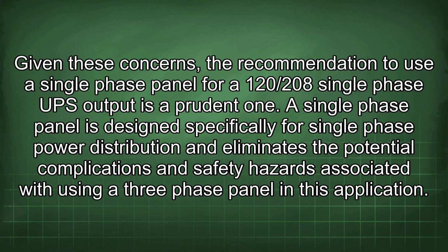Given these concerns, the recommendation to use a single-phase panel for a 120/208 single-phase UPS output is a prudent one. A single-phase panel is designed specifically for single-phase power distribution and eliminates the potential complications and safety hazards associated with using a three-phase panel in this application.